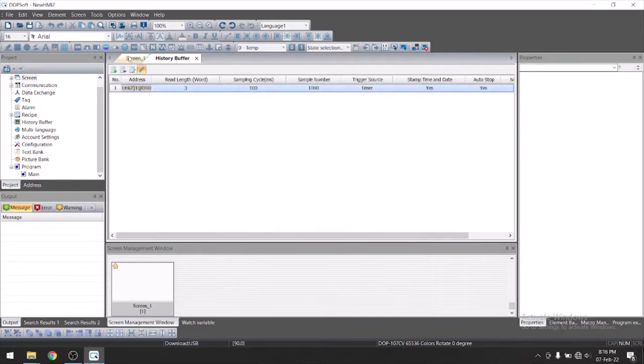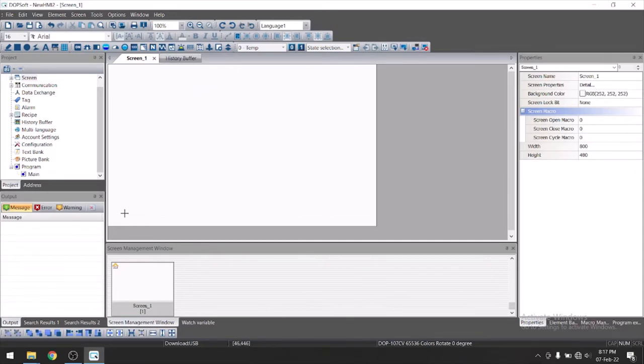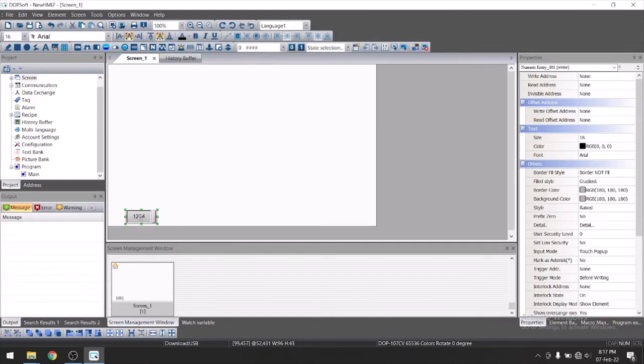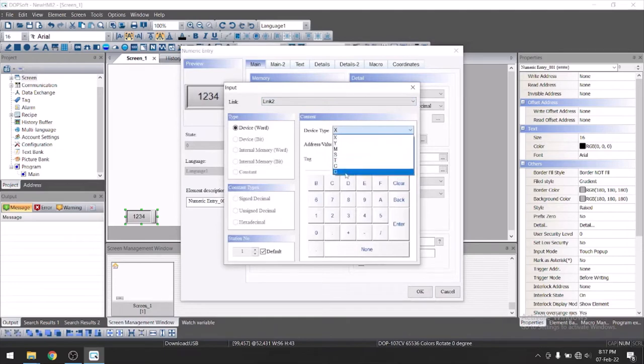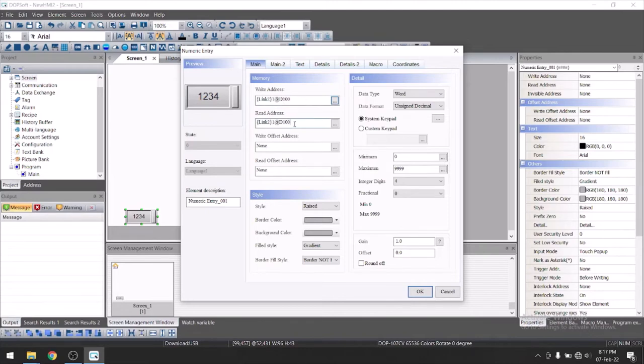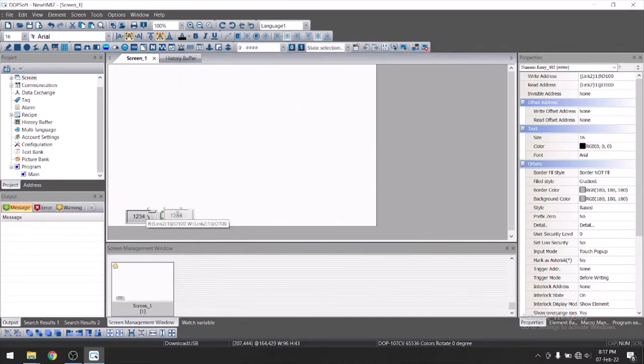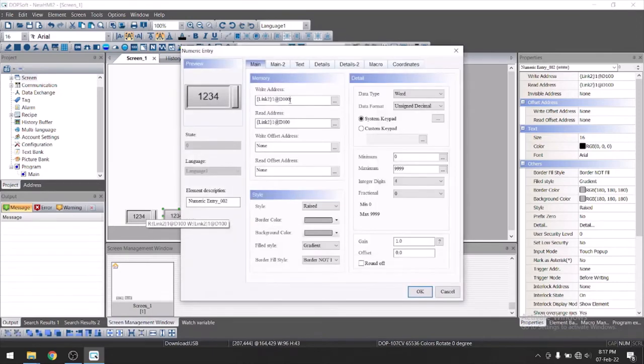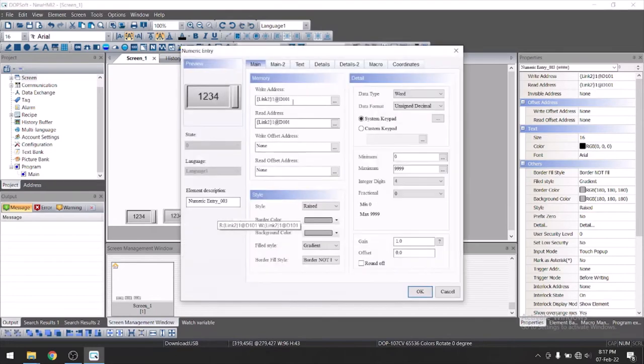Now just go to screen. First we will take three numeric input here. We will have a numeric entry. Give the address. First address is 100, give the D100 here. You need to use next three subsequent address. I will just copy and paste this address here. Write address is D100 and read address is D100. Click on okay. This is first quantity. I will just copy paste. We will modify the address, that is 101. This is second quantity. And this one is third, 102.